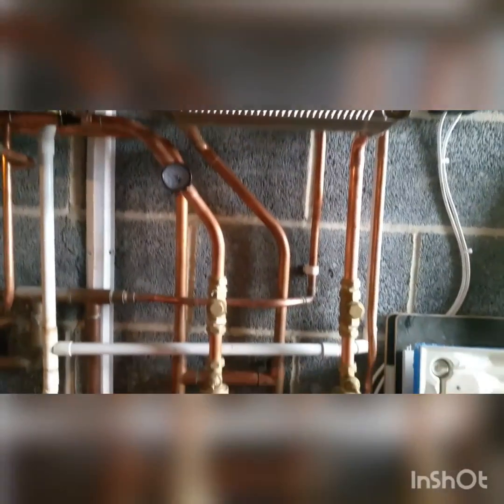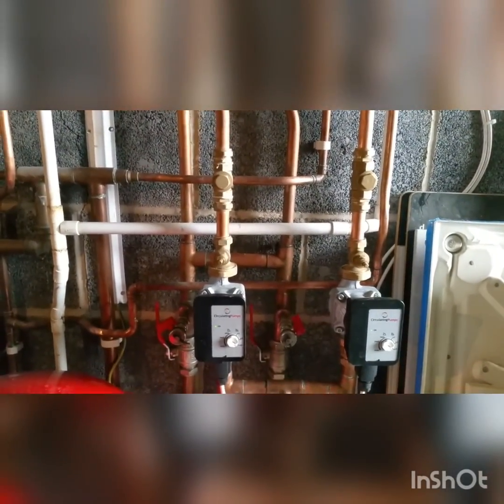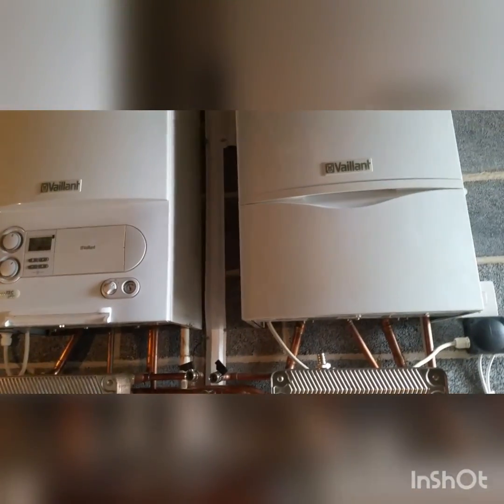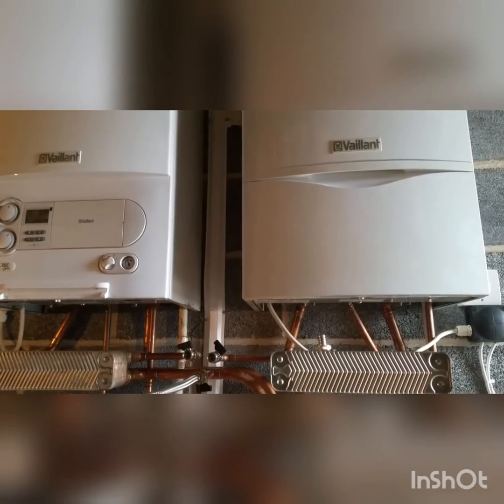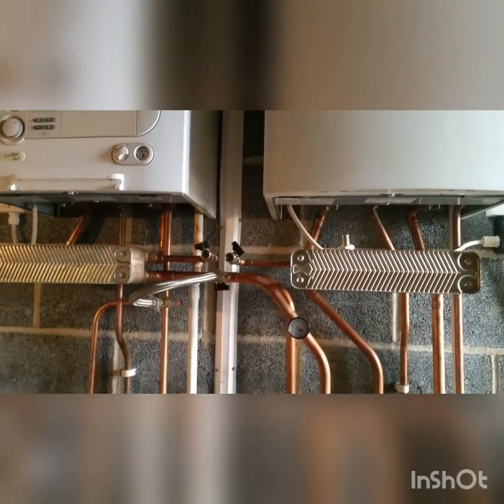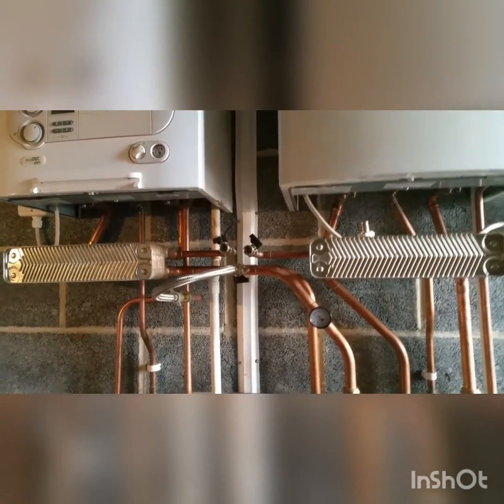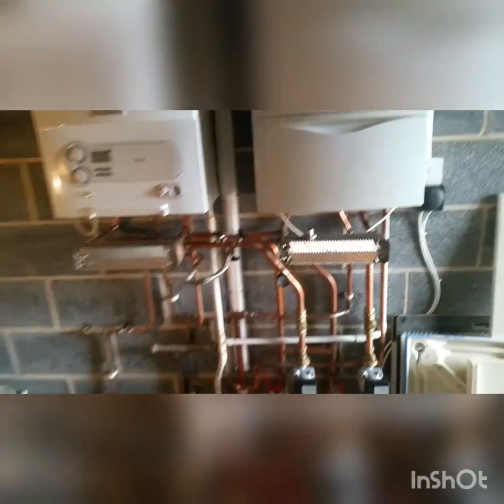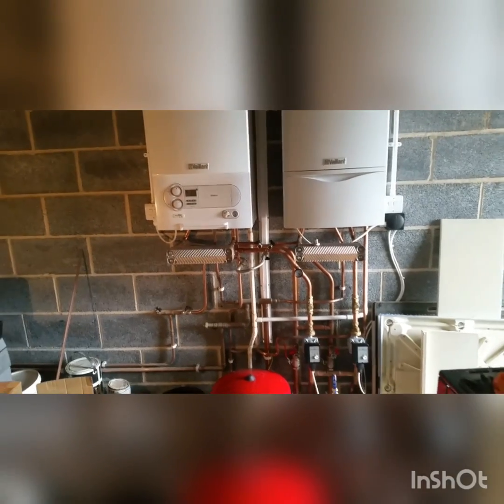It's a very large house, underfloor heating throughout, boilers aren't cascade control, they'll both get the same signal for on at the same time, and they both run at high temperature. We've not gone for weather comp here because it's the wrong manifolds and there's all sorts of complications with pipe sizing. But overall quite tidy.